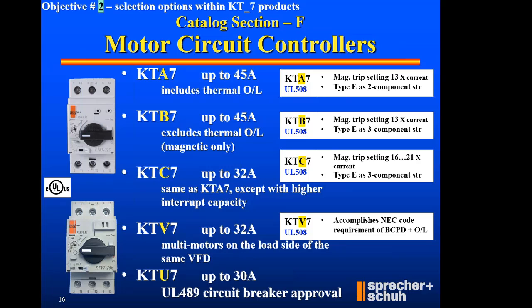So those KTA, B, and C are very similar products. KTV is in Victor. I get an opportunity to dive into it on the next objective, but I'm just acknowledging that KTA, B, C, and V is in Victor are UL 508 approval devices. So those are 508 devices. And then at the bottom of the slide, I've got a KTU as an underdog. And actually that carries a UL 489 circuit breaker approval. So that is indeed a circuit breaker. However, I got a slide later that says I can only go up to 30 amps, and that is for non-motor loads. So I'll kind of explain that in just a second.